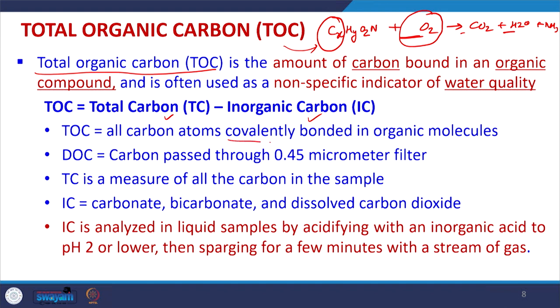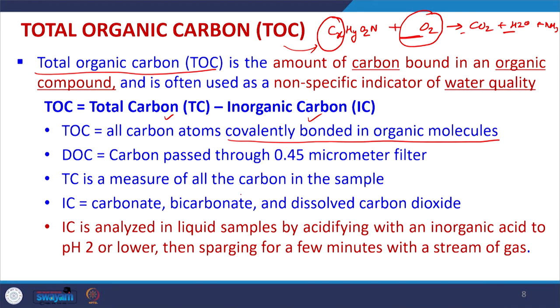TOC represents all carbon atoms covalently bonded in organic molecules. There is also DOC (dissolved organic carbon), which is the carbon passing through a 0.45 µm filter. TC measures all carbon in the sample, and IC (inorganic carbon — carbonate, bicarbonate, dissolved CO2) is analyzed by acidifying to pH 2 or lower and sparging with a gas stream. Modern TOC analyzers measure total carbon and inorganic carbon separately and report TOC by difference.